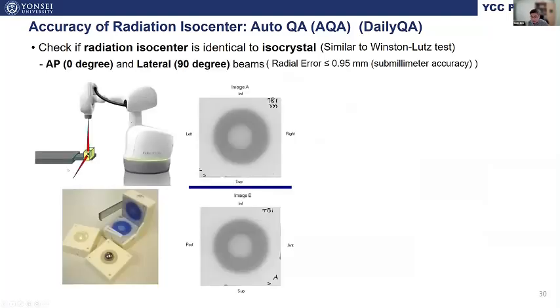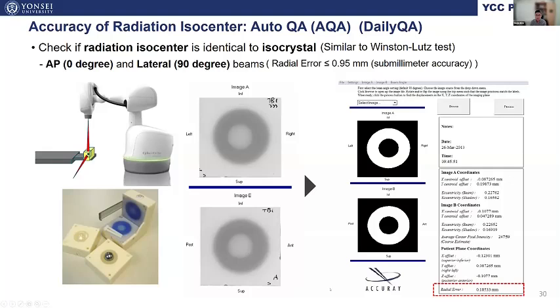Then we need to see if the path calibration was accurately conducted. The first step is called A-QA, which is similar to the Winston-Lutz test that identifies the coincidence between radiation and mechanical isocenter. And the purpose of A-QA is to ensure the accuracy of radiation isocenter after path calibration. It delivers radiation to a cubic phantom having a metal ball inside at two different robotic arm angular positions, 0 and 90 degrees, in a coplanar setting. And the difference between the two isocenters is computed, which needs to be of sub-millimeter accuracy, as seen in the following.